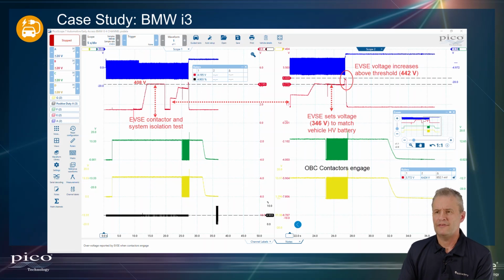Notice then how the 408 volts drops back down to 0. What the EVSE is actually carrying out there is that isolation test. If you remember, there was a tick on the charger display, I think it was a safety check message - that's exactly what's going on here. It's happy with the power cables up to the onboard contactors - there's no detection of a short circuit, so we are good to go. That's our safety check complete.